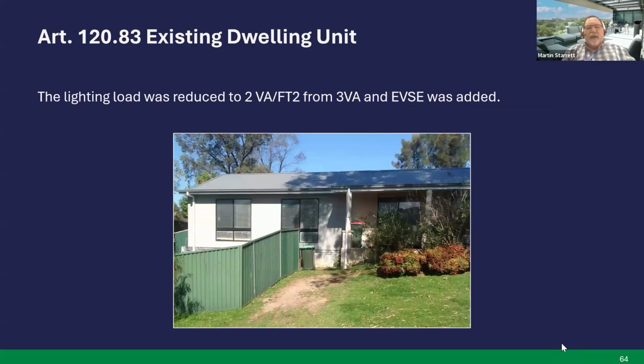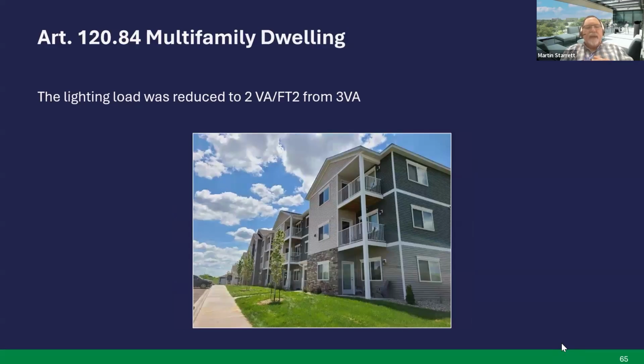Next slide. Existing loads, 120.83. In that article, it was also reduced from 3 VA to 2 VA. An electric vehicle was also added to that article. Next article. There you go. Same thing, 120.84 multifamily. The lighting load was reduced to 2 VA from 3 VA. Next slide.